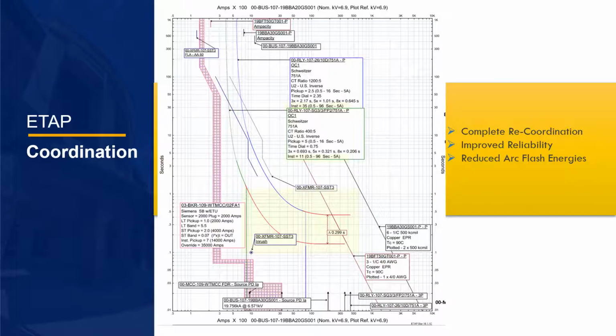The first steps in the relay replacement were to identify the relay manufacturer, model the electrical system in ETAP, and perform a system coordination study. The graphic we are looking at here is one of the many time current curves, TCCs, that were used to analyze the system protection response, calculate the worst case arc flash incident energies, and decide the protective relay settings.